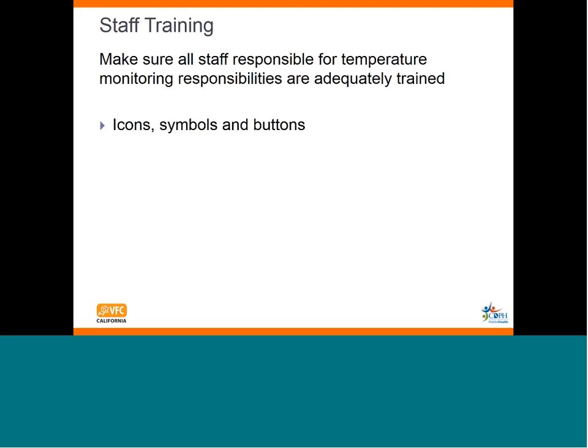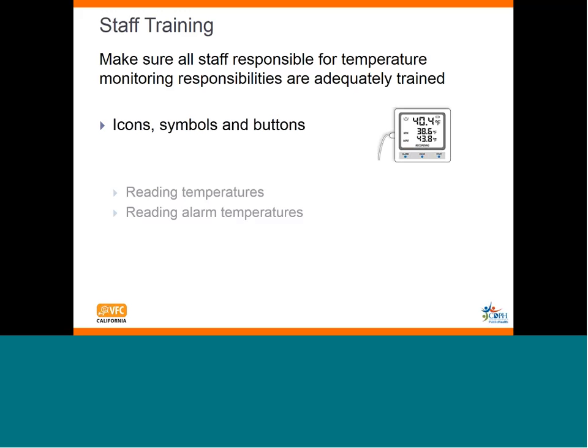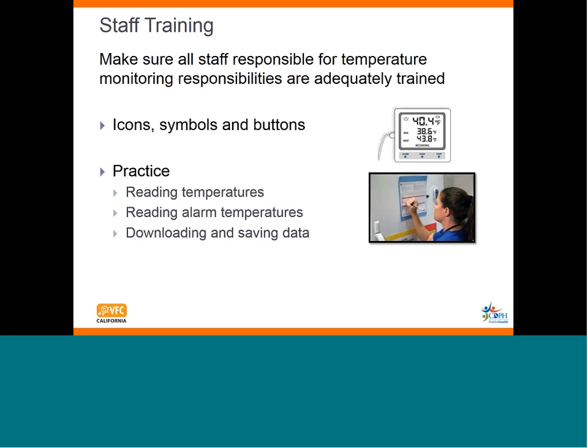Staff should know the meaning of all icons displayed on the unit's display screen, including low battery indicators, and should practice and demonstrate proficiency before using a new unit or system. To record temperatures on VFC program logs, practice should include reading temperatures, identifying alarms in the unit, reading alarm temperatures, properly starting and stopping the unit, and downloading and saving data.